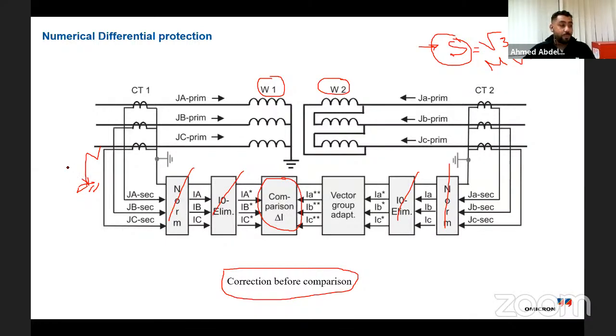So I need a closed path for the current to flow, a closed loop. So what will be the direction if I have a fault here? The current will flow in the phase, then it will go to the ground, and from the ground to the other side. But the fault is already outside the protected zone. So what should happen? I should not trip. The relay shouldn't trip.